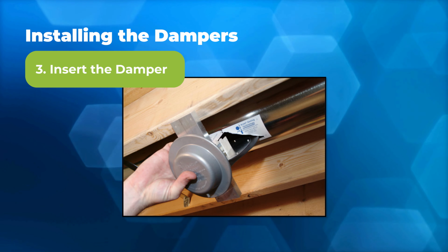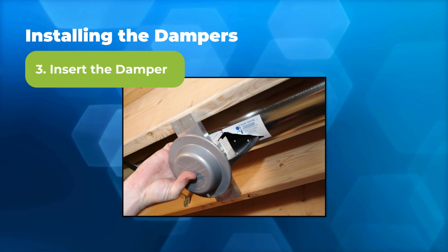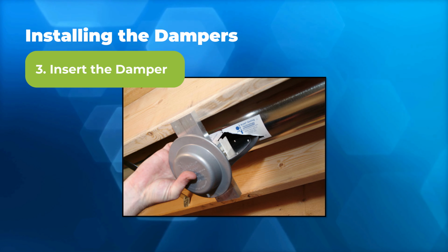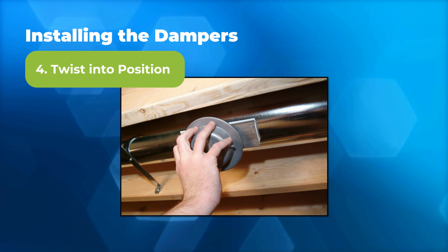Once you get your hole cut out, you're going to enter the damper in sideways and hold the blade with your fingers so it stays in the closed position. Once you get it inside the duct, you just do a 90-degree turn with it.